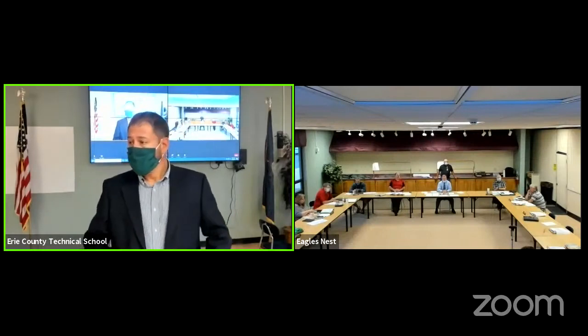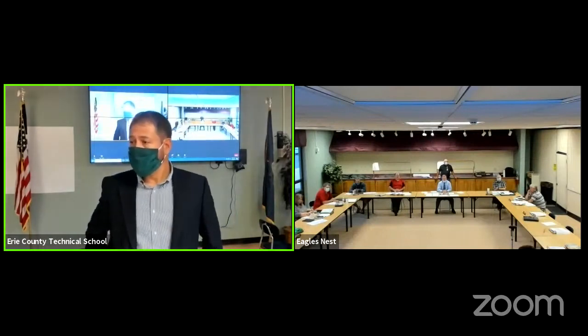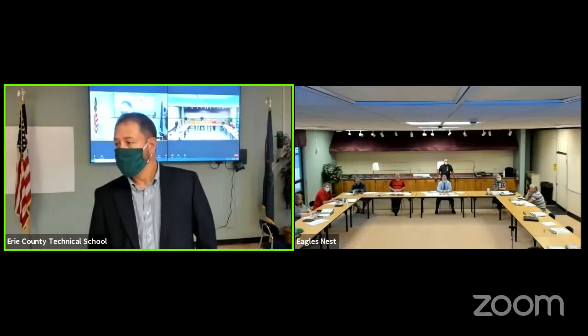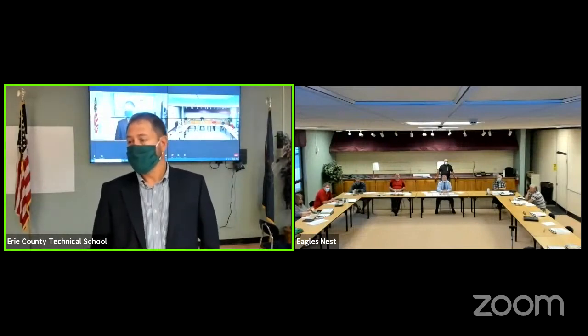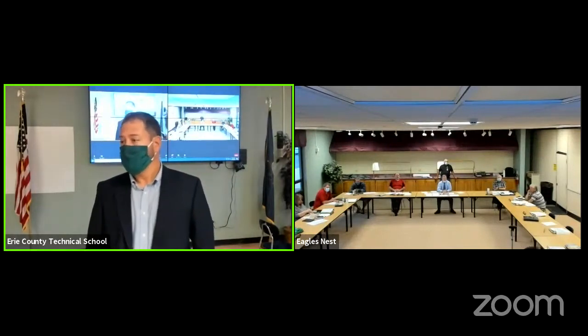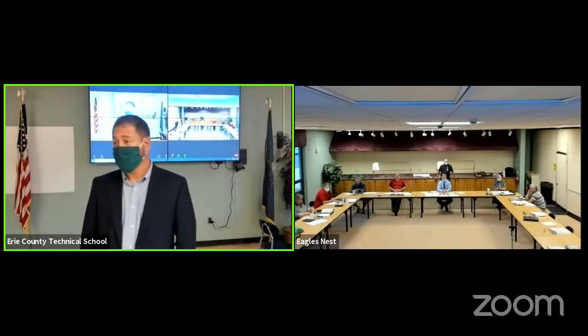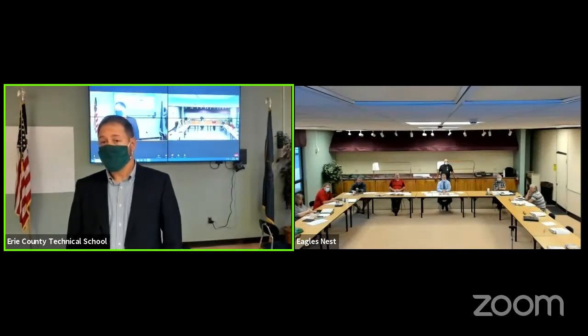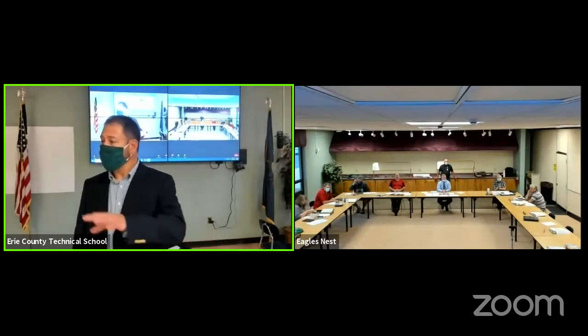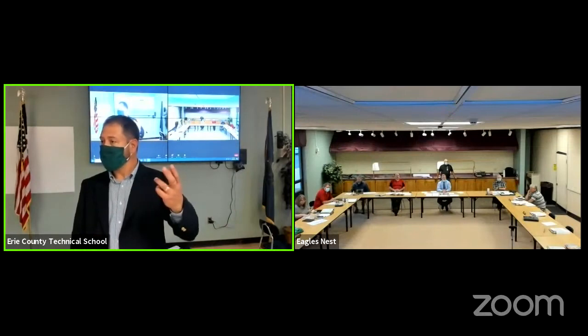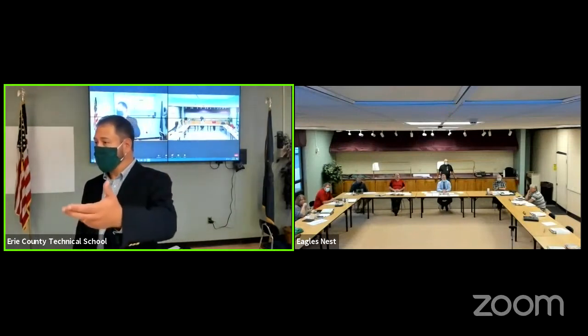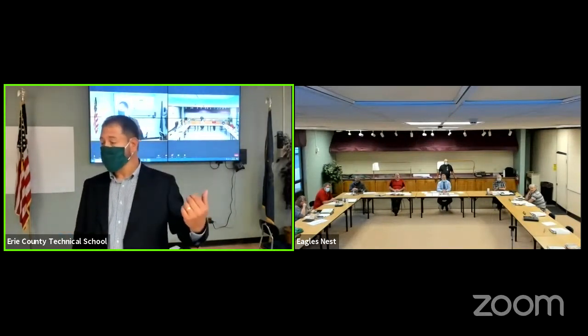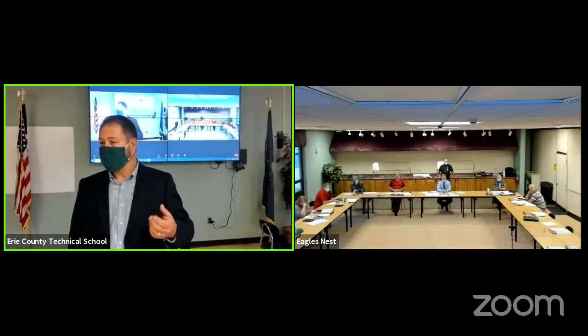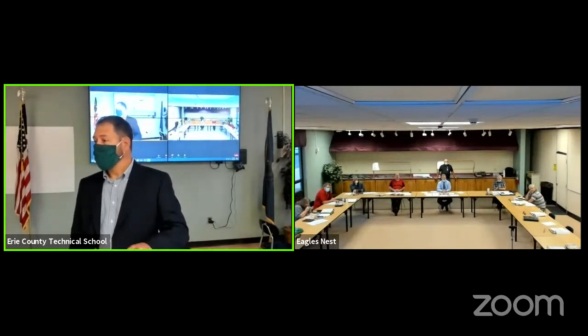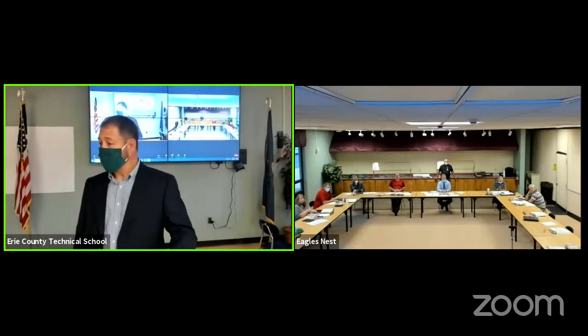Are there any return plenum areas — open areas — in this new design? Everything's going to be ducted. We typically like to duct everything, especially in a building like this where you have different things going on in the various spaces. When you do return air plenums, you start transferring smells from one program to another. We'd prefer to duct it, and that's how we have it in the project currently.